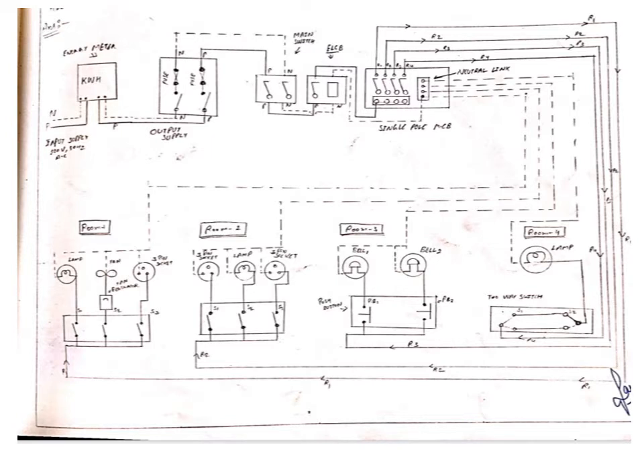Here, as we have seen in the question, we have to connect four subcircuits. So we have taken four points for this distribution board, that is, we have selected a 4-way distribution board. From that bus bar, four single pole MCBs are connected in phase. So we have taken one phase from here and given it to subcircuit 1.